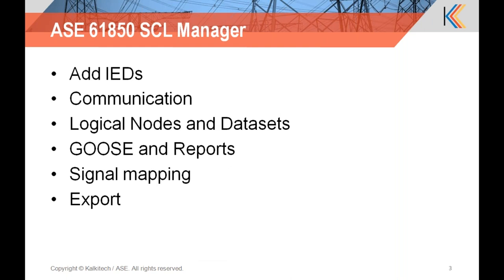For the SCL manager functions, I will show you how IEDs are populated in the tool and how communication addressing is configured. We will also see the logical nodes and datasets view in the SCL manager tool. We will use multiple IED configuration, so you will be able to see how multiple IEDs are handled. We will also see the GOOSE addressing and reports addressing. And finally, the signal mapping, which is the primary function from a data exchanging perspective. We will try to spend more time there and cover aspects of signal exchanging, and finally see the export of configuration from the tool.